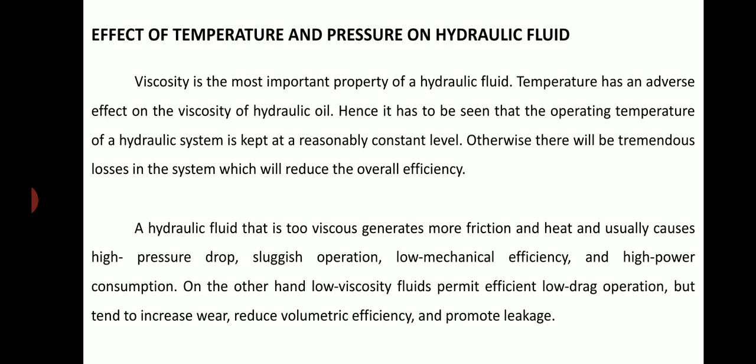A hydraulic fluid that is too viscous generates more friction and heat, and usually causes high pressure drop, sluggish operation, low mechanical efficiency, and high power consumption. On the other hand, low viscosity fluids permit efficient low-drag operation but tend to increase wear, reduce volumetric efficiency, and promote leakage.